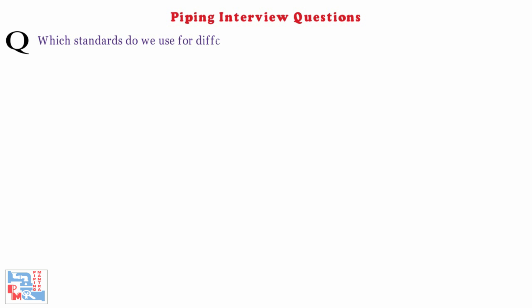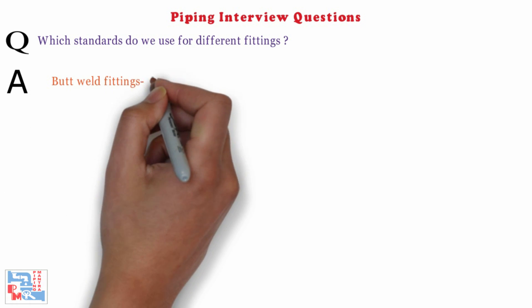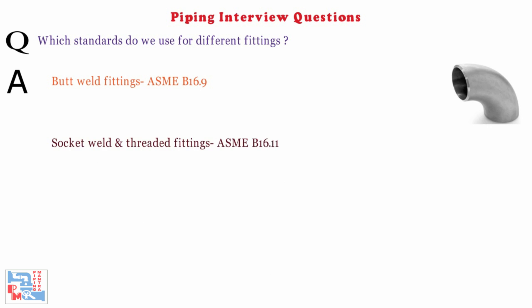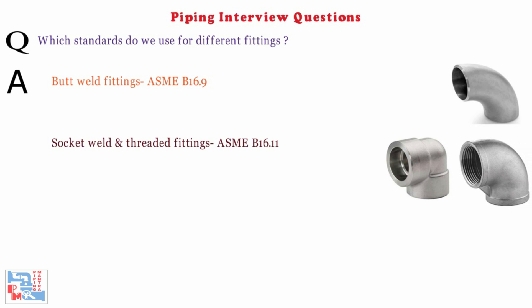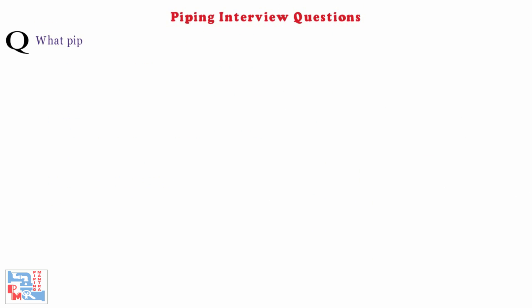Next: which standards do we use for different fittings? For butt weld fittings, ASME B16.9 is used. For socket weld and threaded fittings, we use ASME B16.11. For swage fittings, we use MSS SP95.